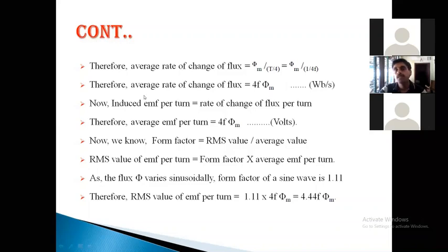So if you see, the average rate of change of flux is equal to 4f phi m, 4f into phi m. Therefore the induced EMF per turn, just like you calculated in the generator, is the rate of change of flux per turn, equal to 4 f into phi m. Therefore, if you take the form factor, RMS value by average value, the RMS value of the EMF per turn is form factor into average EMF per turn. Therefore, 1.11 into 4 f phi m. This is the EMF per turn.